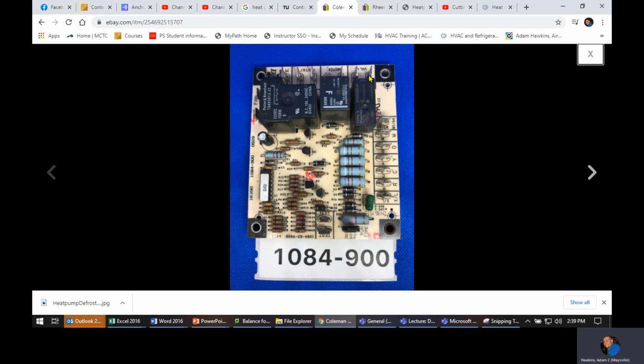So this one will have a power out and a power back, assuming one's common, one's hot, and it probably doesn't matter which one. Switch, this is probably some sort of pressure switch. So this is going to be power. So these are different. This one you can't jumper because one side of this is going to go to common, the other side is going to go to red, go to hot. This switch, if it's just a basic switch, you could jumper that. If it is just a thermostat to where it's made, or wait, sorry, pressure switch, sorry. If it's just a pressure switch, so it's not a transducer or something like that.